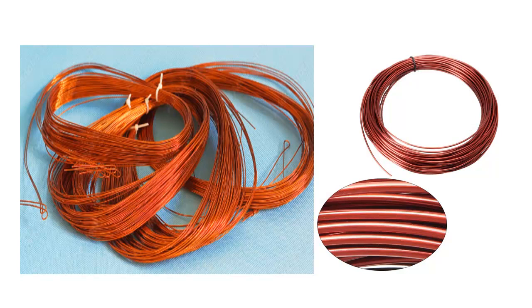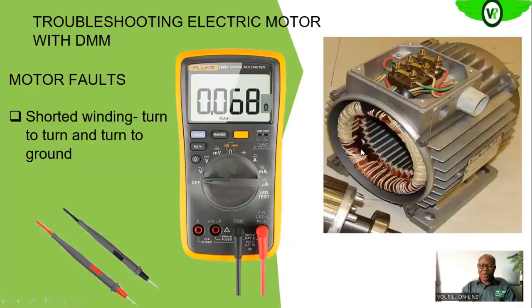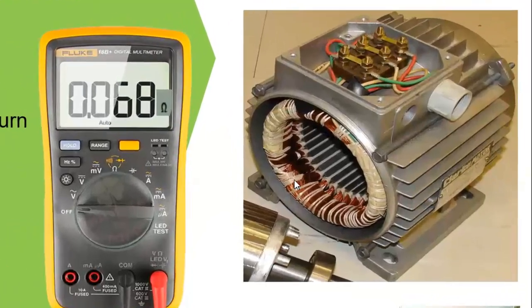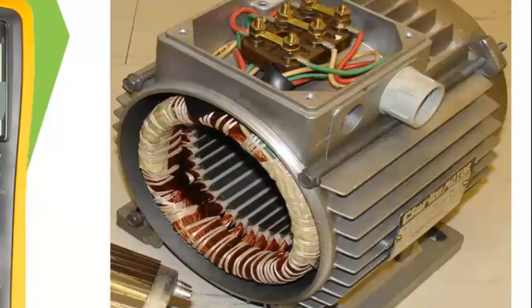So maybe due to imperfection or operational problems, there may be breakage in the insulation. This copper wire that you are seeing is insulated. Each strand of it is insulated. That is why it is called insulated copper wire, and that is what we use in doing our rewinding. So whether the wires are on each other doesn't matter, because they will not make contact with each other since they are insulated. Since they are insulated, they don't have any connection.